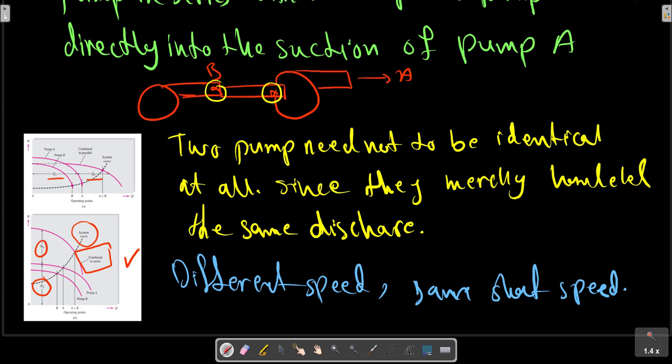The need for a series arrangement implies that the system curve is steep. It requires higher head than either pump A or B can provide. The combined operating point head will be more than either A or B as shown in the picture, but not as great as their sum.